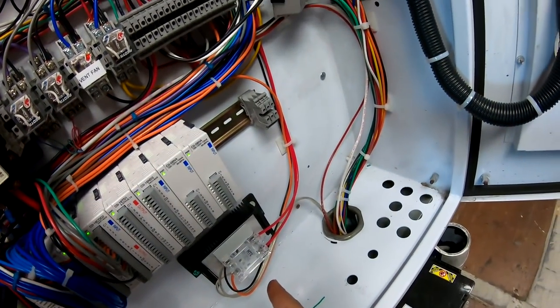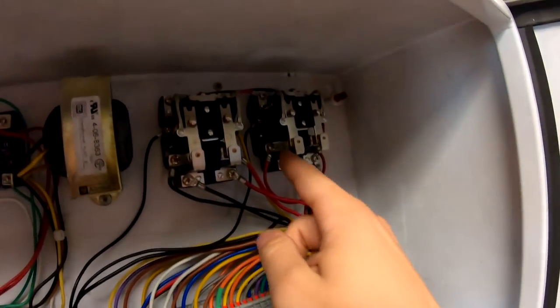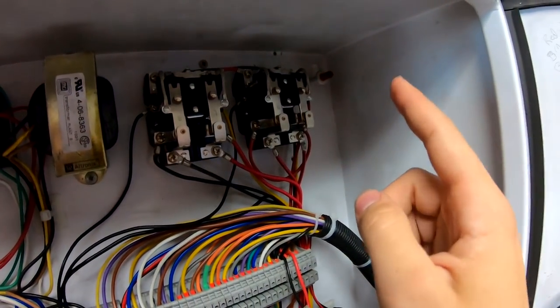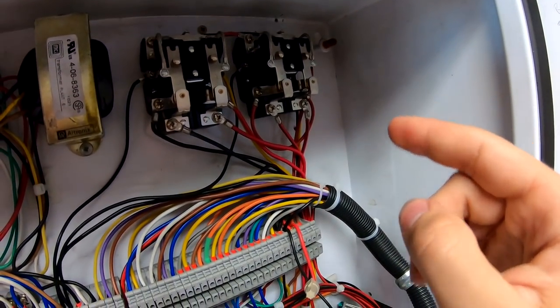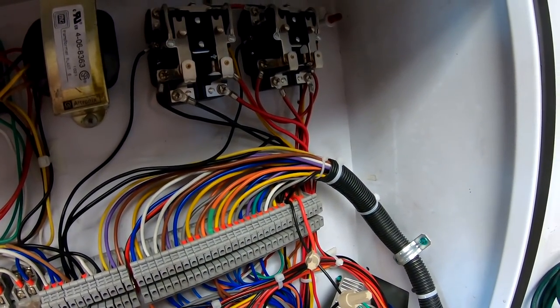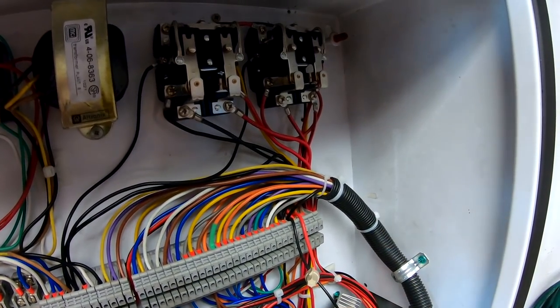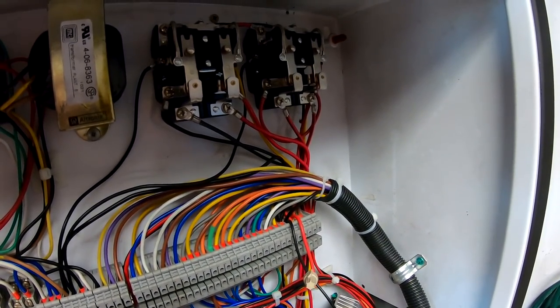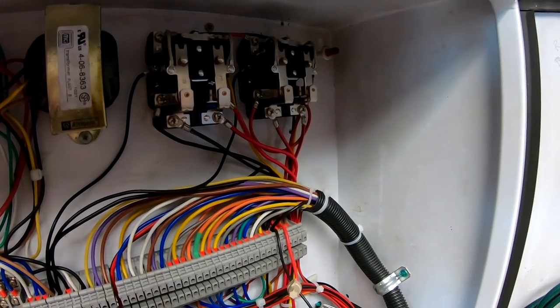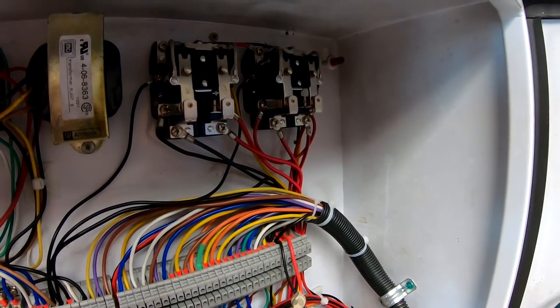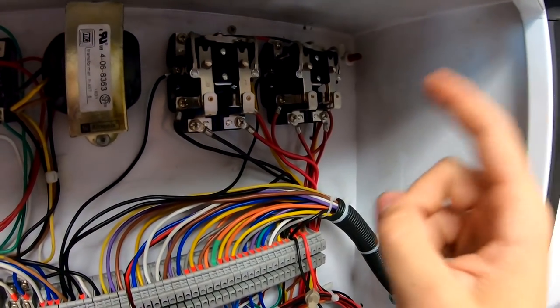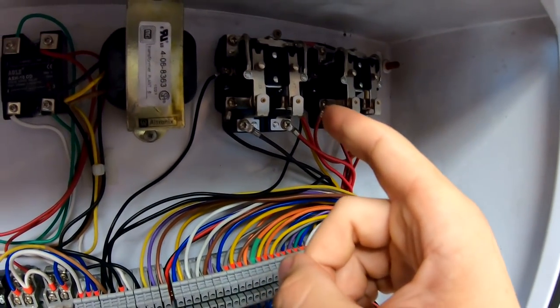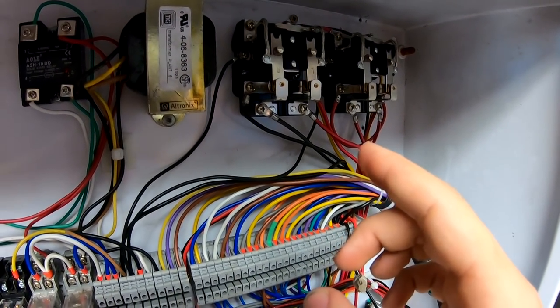And pretty much what this relay right here does is these two wires on the bottom right here are connected to that solid-state relay, but then we have a jumper across the other side. So all this relay does is it either goes through the solid-state relay or through the jumper. And when it's through the jumper it's turning it on 100% of the time, so you get 100% of the power going through.